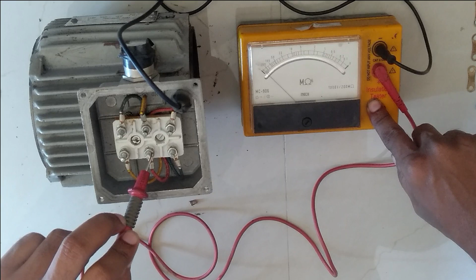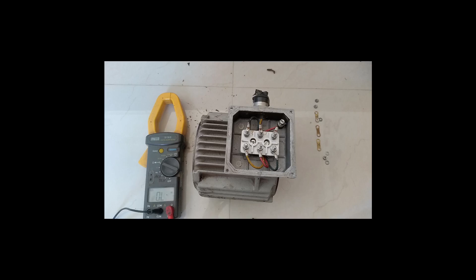So here we go, phase to body. We are checking all the phases. With the first phase you see it is infinity, the insulation level is infinity. With the second phase also the Megger value is infinity, and with the third phase it's the same, the Megger value is infinity. So by this we come to know that none of the three windings have contacted the body of the motor. The winding is burned to a great extent, but the winding is not connected electrically to the motor body.